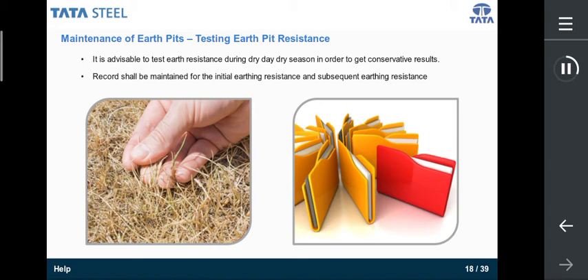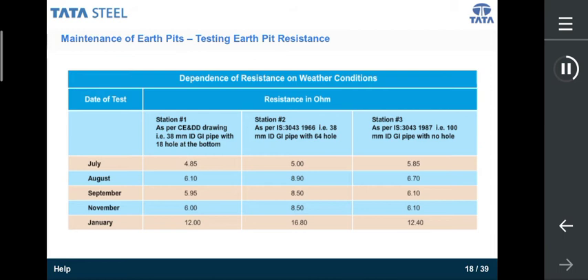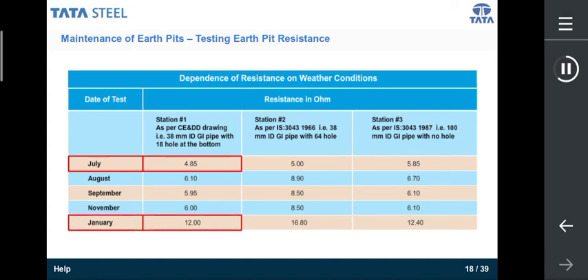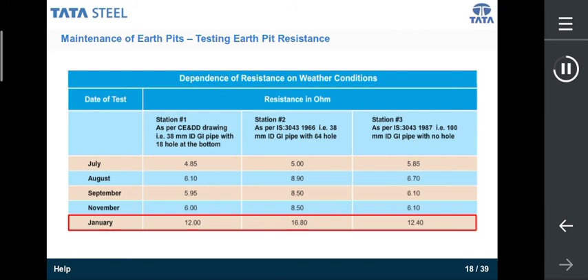In this context, it is important to have a look at this table. The table here conveys how the resistance of an earthing pit varies depending upon the seasonal condition. For example, if you take a look, the value of each month differs. While there is a lower value in July, January has a higher value. Therefore, you can see that the resistance values vary with the season. Also, if you look at the last row, the values have been consistently high in the month of January across all the 3 stations. Therefore, maintenance of each earth pit should be done when the resistance values are high. Further, this maintenance should be done during the dry seasons only, that is between January to March.